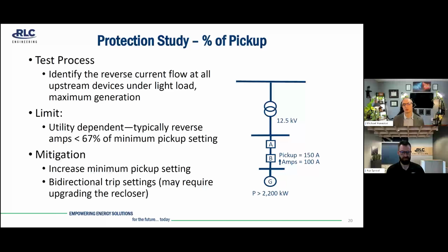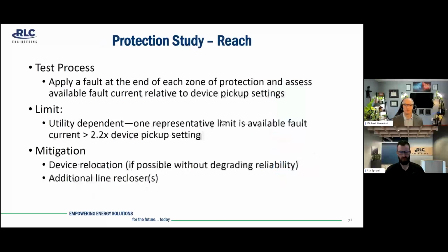And that's where you start getting into more protection adjustments that you might need to make. So here we see mitigation being increasing that minimum pickup. If you can't increase that minimum pickup for any number of reasons, you might need bidirectional trip settings. And that could mean replacing some of those devices such that they'll have that capability.